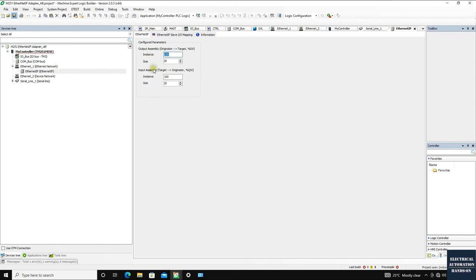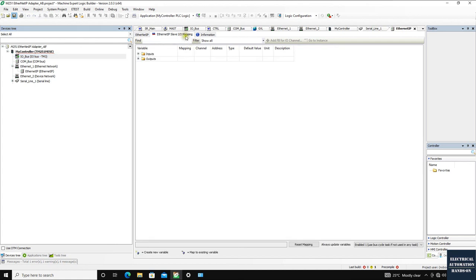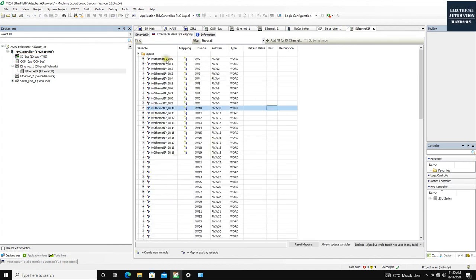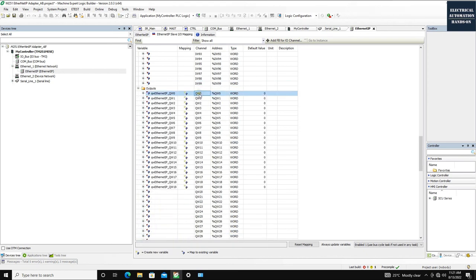We should not change the assembly instance numbers, but we can change the size. For example, I'll set both input and output to 100 words — that means we're communicating 200 bytes in each direction. Then we go to the EtherNet/IP slave I/O mapping, where we can see input starts from 0, going from 0 to 99 (100 words), and output similarly from 0 to 99.